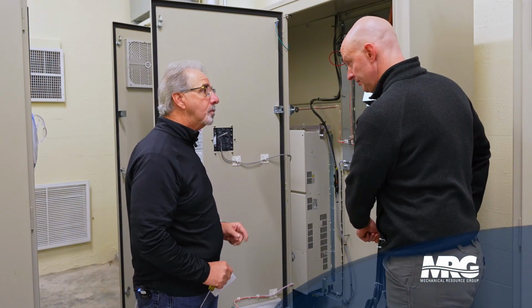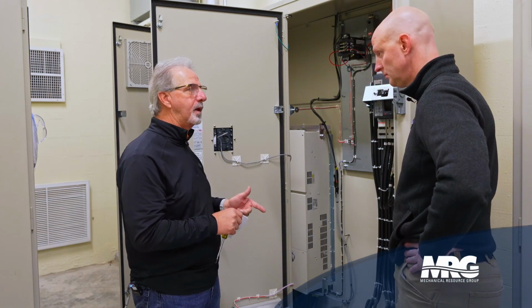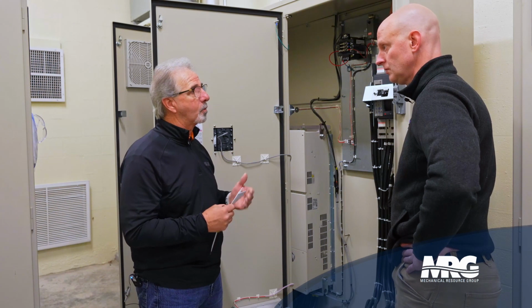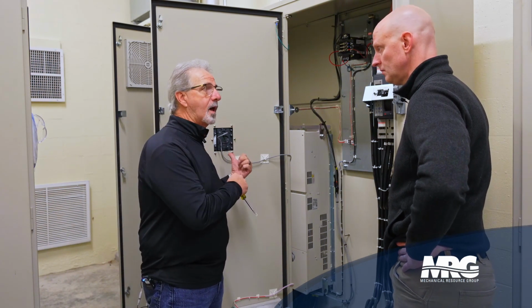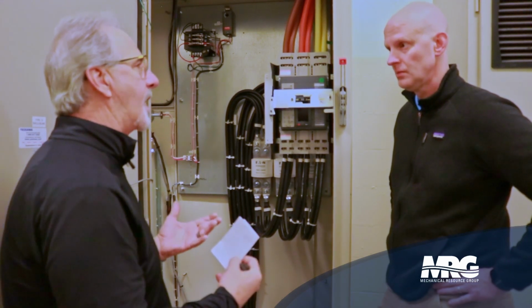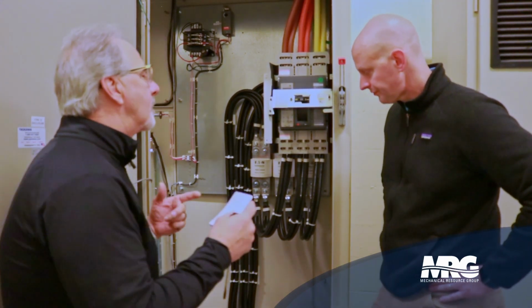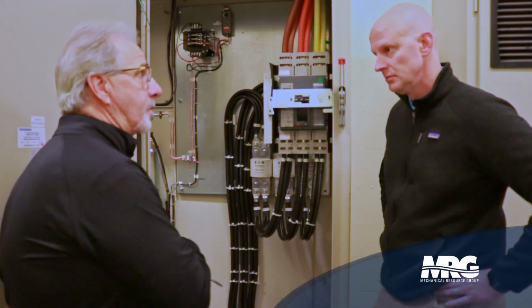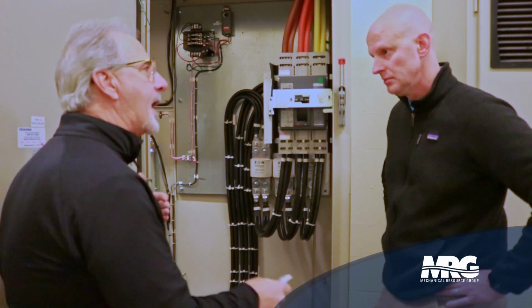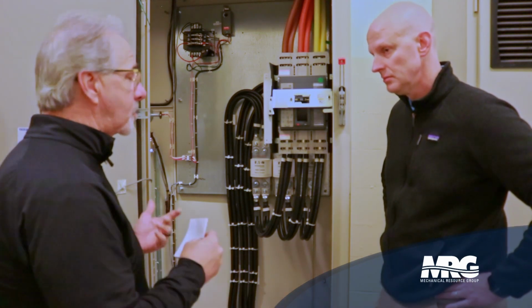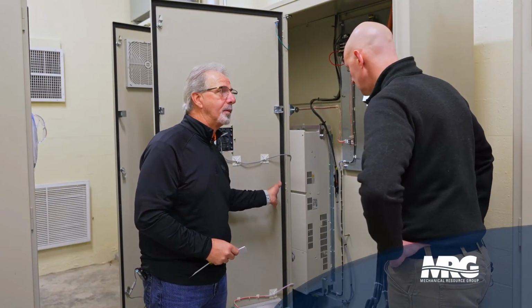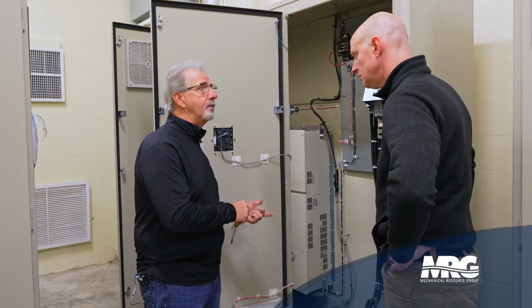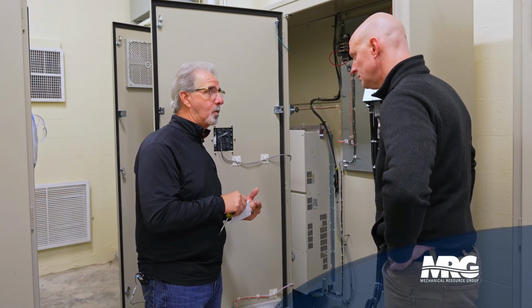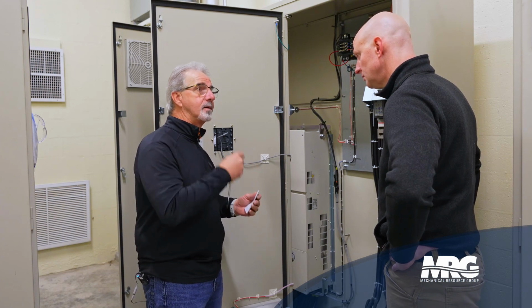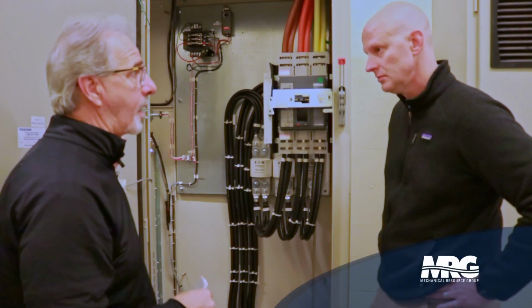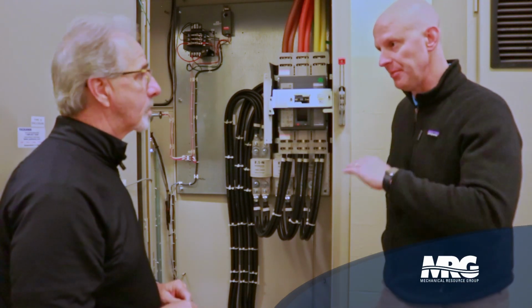So the line resistor? This is the line reactor down here. This adds 3% impedance. So what this means is I'm adding resistance to that harmonic waveform to try to slow it down before it hits the active filter. I'm trying to give it a better sine wave. Yeah. Okay. So that's what that does. Now, in addition to that would be the 5% that I already have internal in the drive itself. So when you add the two together, that gives me 8%. That equates to, remember we talked, 33% at the input terminal of the drive. The 8% impedance that we have takes our 33% and knocks it down to 21%. 21% harmonic content times 3 is much more manageable for the harmonic filter. Okay. So we're knocking it down to something that's manageable for the filter.